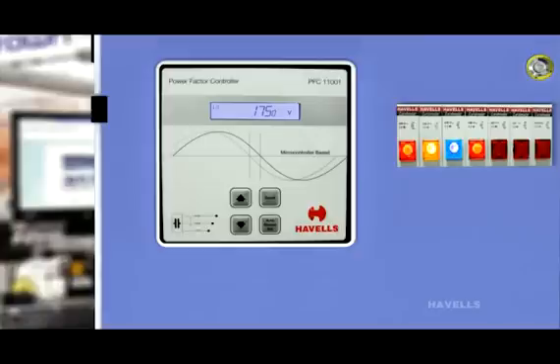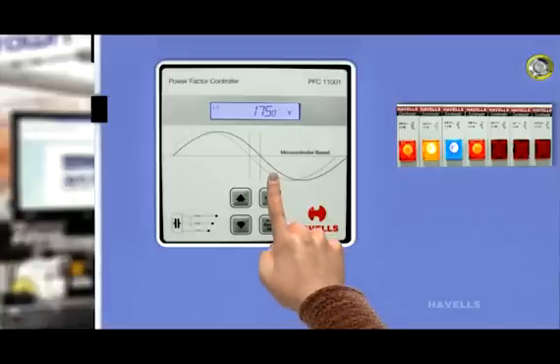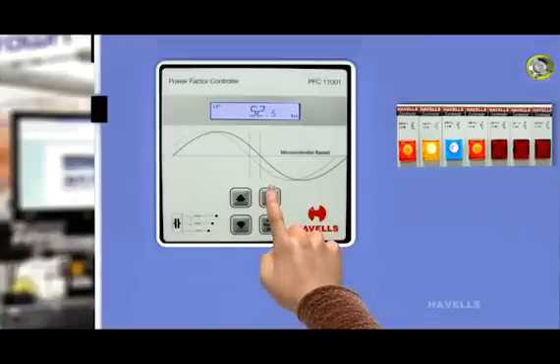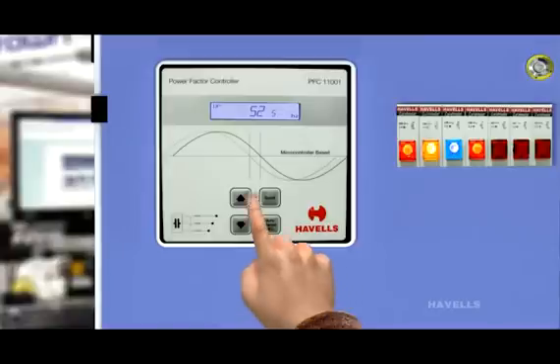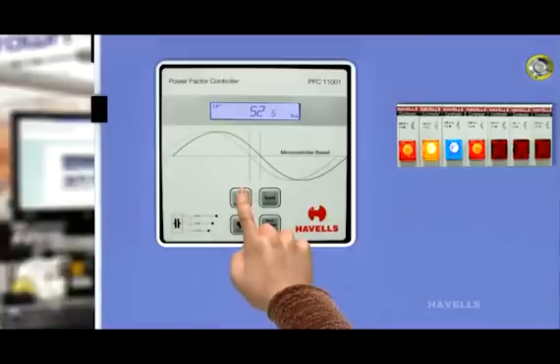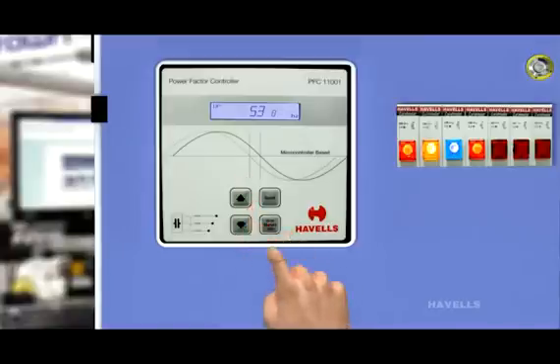Press scroll switch again. Controller shows upper frequency threshold on LCD, which is 52.5 hertz. It can vary up to 60 hertz.